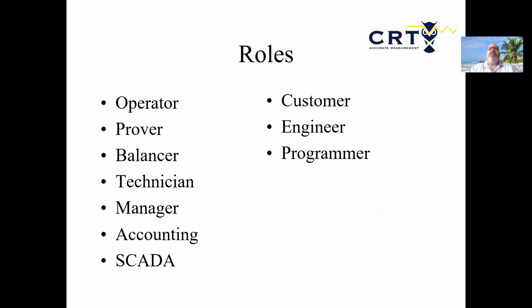So what are the roles we typically see within a flow computer? Well, you've got an operator. What's an operator doing? A lot of different things. We found that an operator at one company may not be the same as an operator in another area. I may have an operator whose only job is to look at the flow rate, and when the report comes out, pass it along, or make sure a batch ended at midnight or 7 in the morning. But other operators may actually have to prove meters, change meter factors, and do some diagnostics. So we look at the roles inside a flow computer and try to create displays and access limits based on these specific roles.